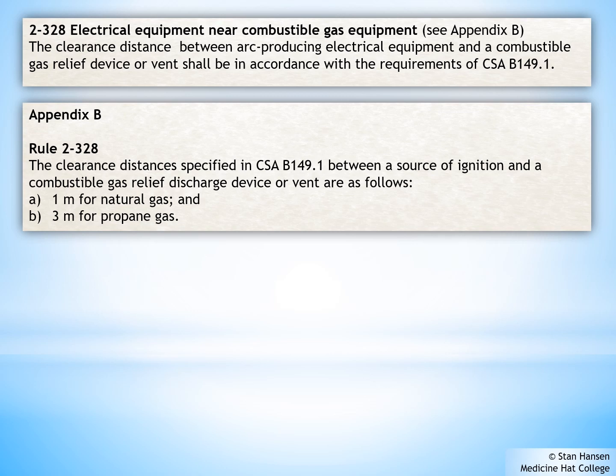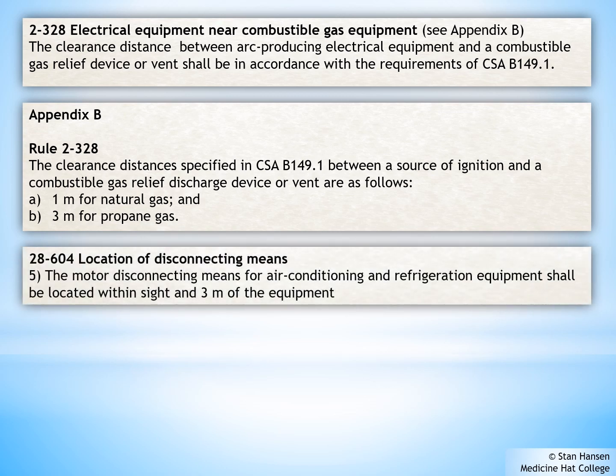The disconnecting means for the air conditioning unit shall be located within sight and 3 meters of the equipment. Typically, when we're doing a rough-in, we want to make sure that we place the disconnect wires somewhere where the air conditioner is going to be. They're easily accessible. Nobody else can turn the air conditioner on or off while we're working on it, so you need to have it within sight. But also keep in mind, you don't want it directly behind the unit because then it might be difficult to access that disconnect.